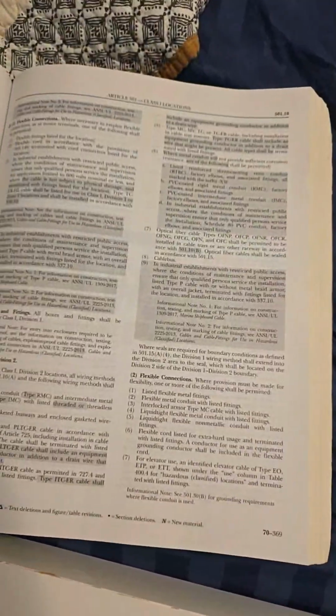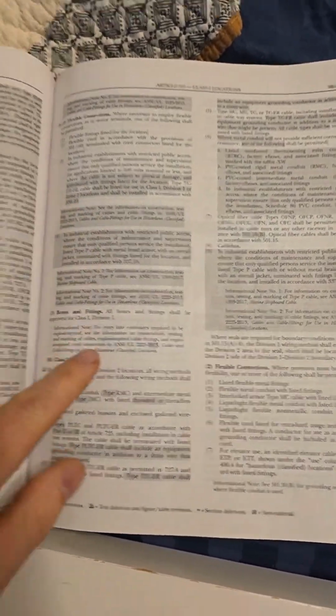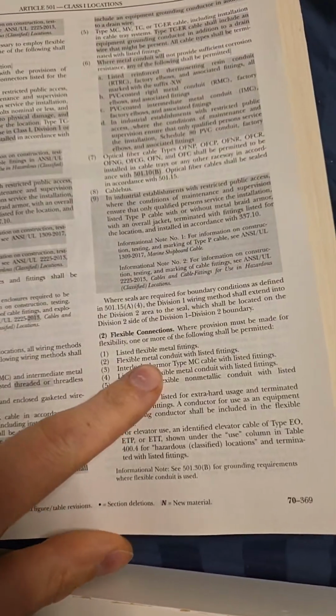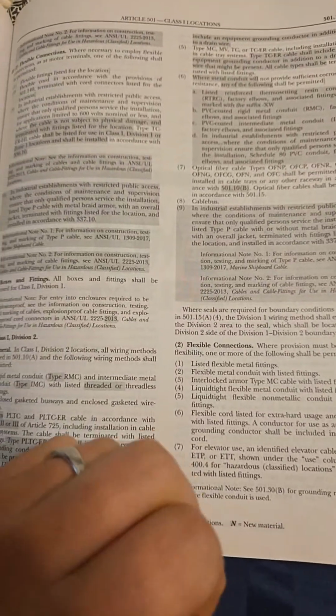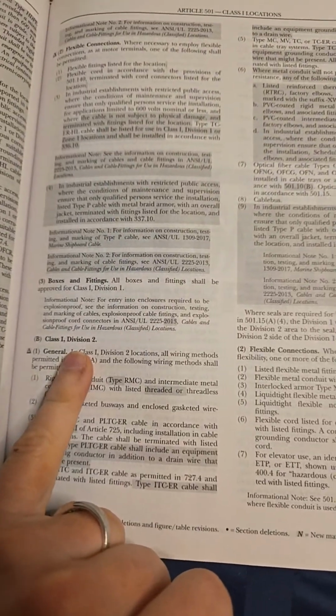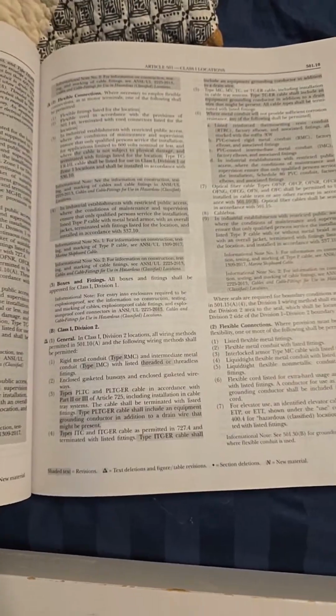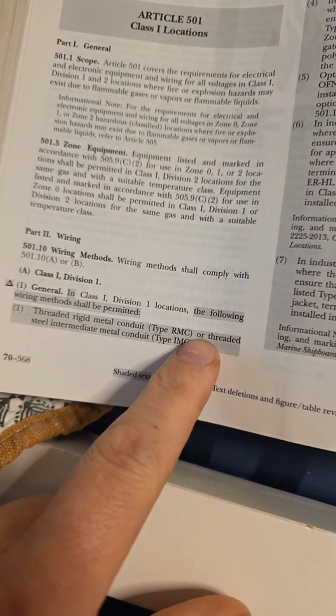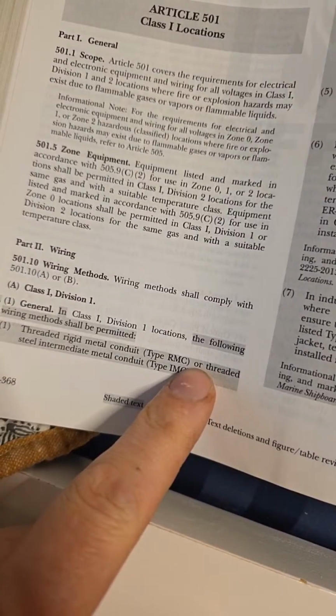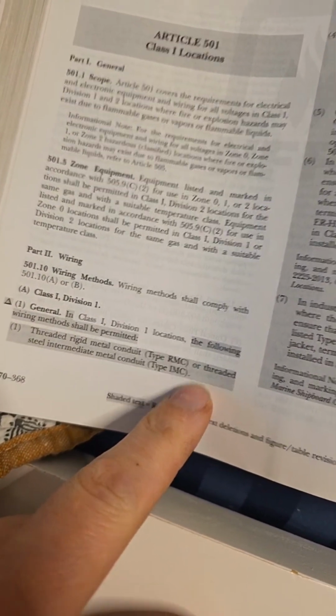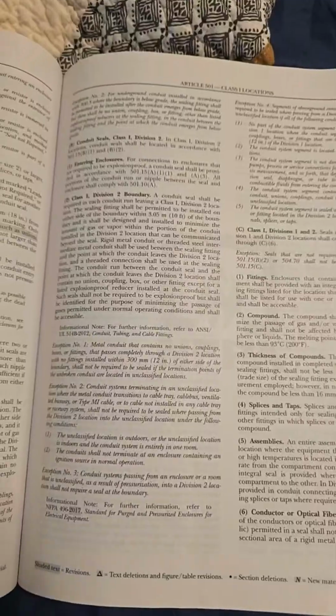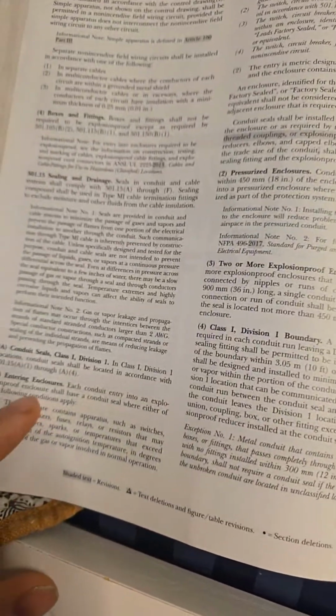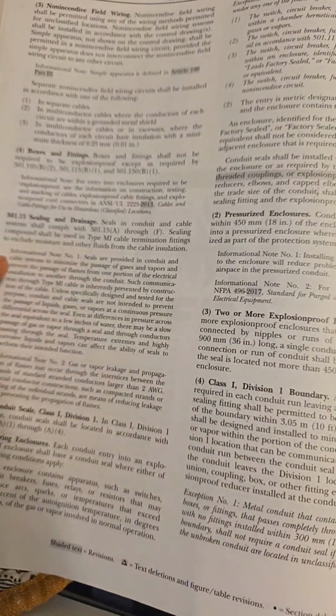Okay, so we're going to keep going because this just talks about the classes. So we're going to get more into the class 1 locations here. And we're going to see we got boxes and fittings. We got flexible connections. We're looking for the seal off. So we got class 1. Doesn't tell us what division though. All it says is the class. And this is the threaded metal, RMC. That's where it shall be permitted. We are looking for the sealing. So there's boxes and fittings. Let's see if we can find something called sealing. There's your boundary, entering enclosures. We're getting close, sealing and drainage. And now we're looking for a thickness.